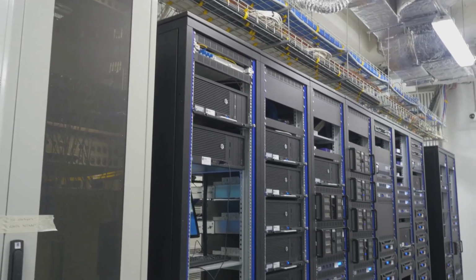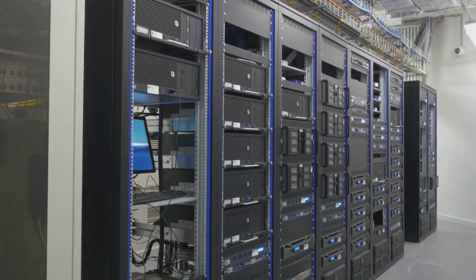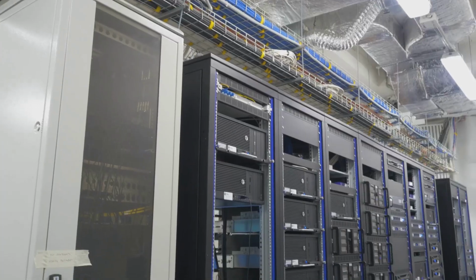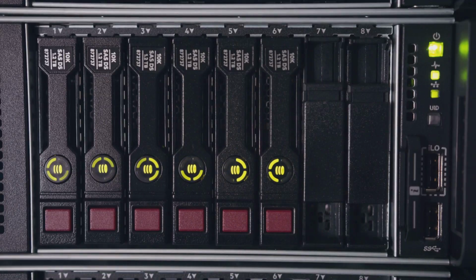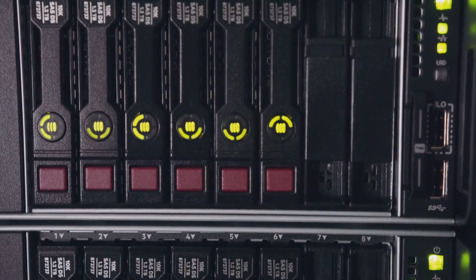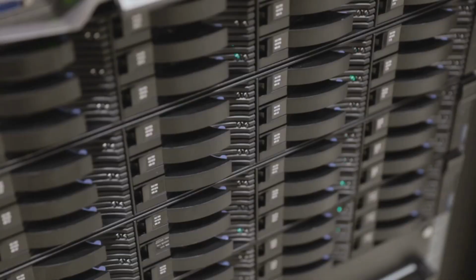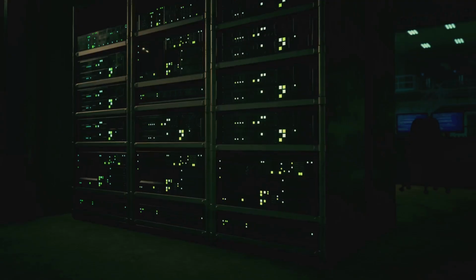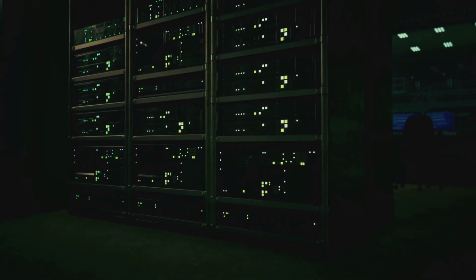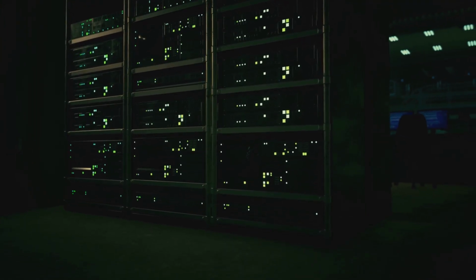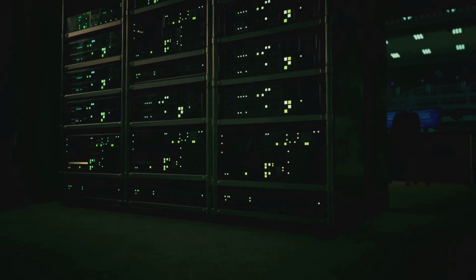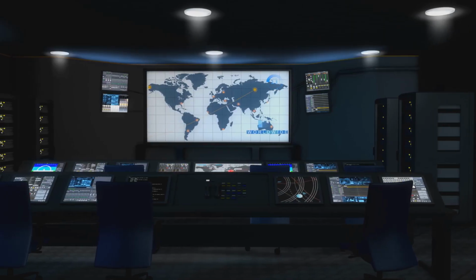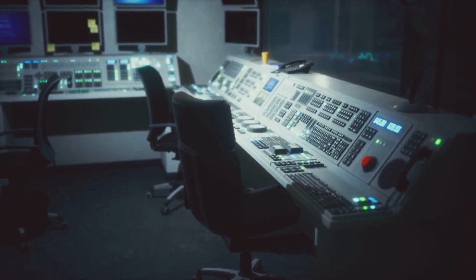Hardware is redundant: two power supplies, so one can fail and the server keeps running. Storage uses RAID, so important data isn't on just one drive. If a drive breaks, data remains safe and the drive is replaced live. For key apps, multiple servers share the job, and load balancers route around failures. You usually don't notice when something breaks. It's digital teamwork at scale.